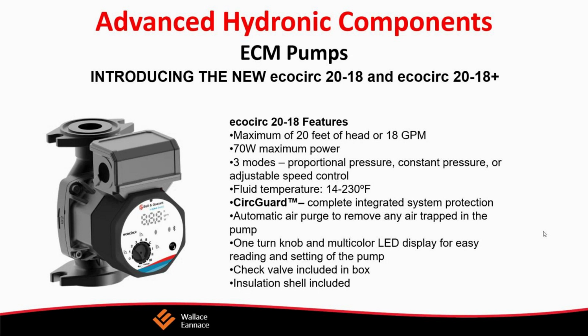So we know that ECM pumps work. But what sizes of ECM pumps are available? Where do they fit? Well, we're pleased to announce that Bell & Gossett has come out with a brand new product. They call it the EcoCirc 2018 and the EcoCirc 2018 Plus. It's called 2018 because it has a maximum of 20 feet of head or 18 GPM, and 70 watts maximum power. Remember, all those other circulators were running at 90 watts. This is 70 watts at full load. Once again, we can modulate it downward, in which case it drops.